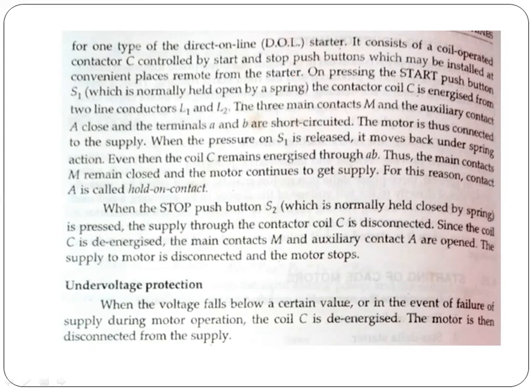When the stop push button S2, which is normally held closed by the spring, is pressed, the supply voltage to the contactor coil C is disconnected. Since the coil C is de-energized, the main contacts M and the auxiliary contact A are open. The supply to the motor is disconnected and the motor stops.